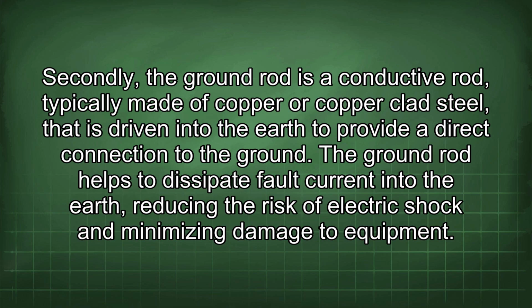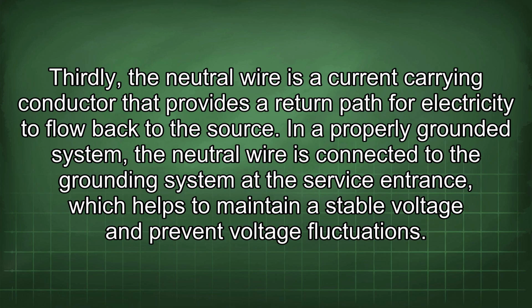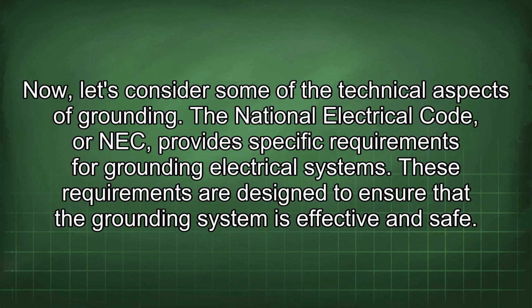The ground rod helps to dissipate fault current into the earth, reducing the risk of electric shock and minimizing damage to equipment. Thirdly, the neutral wire is a current-carrying conductor that provides a return path for electricity to flow back to the source. In a properly grounded system, the neutral wire is connected to the grounding system at the service entrance, which helps to maintain a stable voltage and prevent voltage fluctuations. Now let's consider some of the technical aspects of grounding.